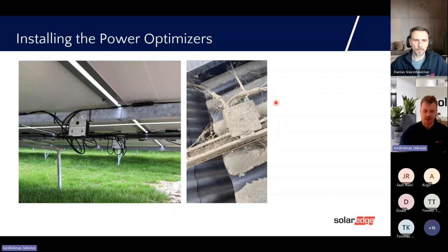And here, as we call it, is a submarine optimizer. It was installed in a place where the water collects, and the installer was asking why it's not working. So one thing, the optimizer is not built as a submarine, right? But another thing is that MC4 connectors are IP65, which is not made to be constantly under water. So take a look at where you install your PV and whether the drainage is okay, because damage can be done. There is going to be no warranty.